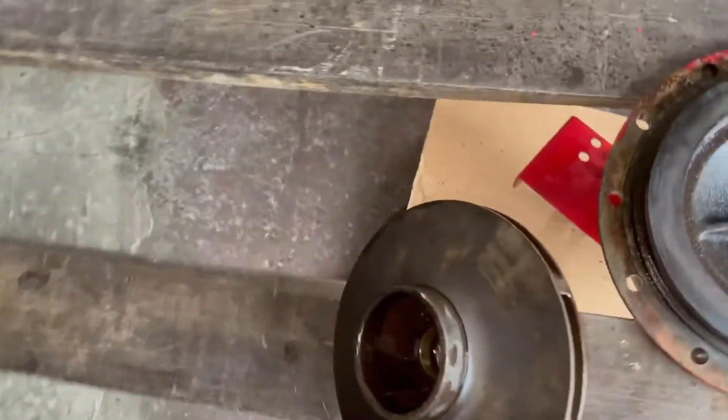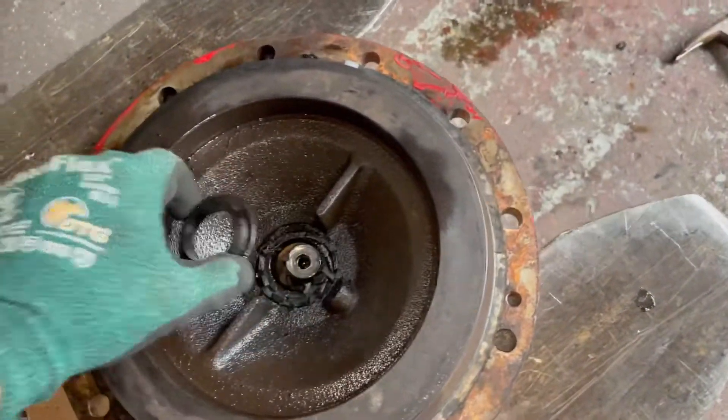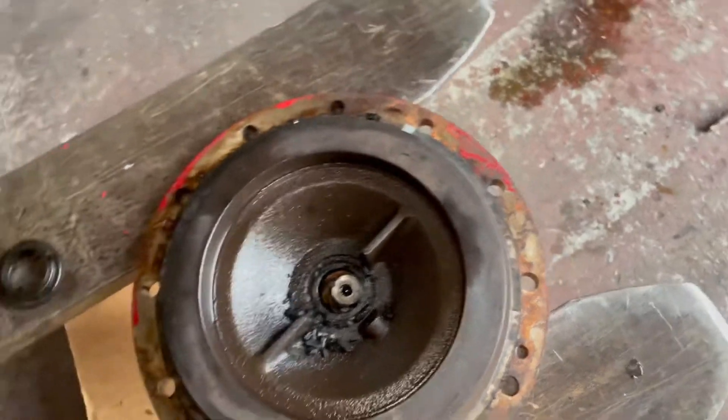So we saved about $500 on an impeller, because that's brass, or who knows what it is. My seal and sleeve are all going to need replaced. I'm going to have to check out them bearings now too.